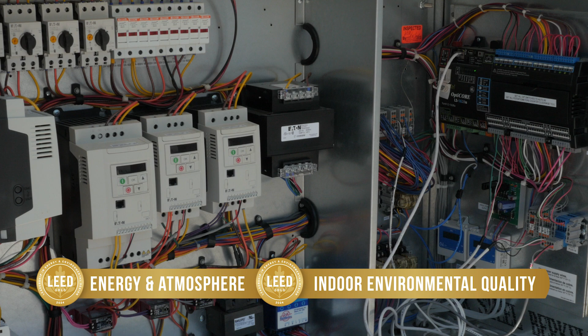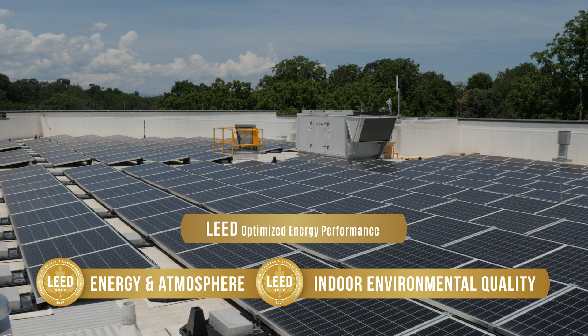Traditional heat pumps have varying levels at which it's too cold to extract heat in freezing temperatures. However, these VRF units can still extract and provide heat at temperatures as low as -10 degrees. This is the first installation of VRF units in the city, and they're the reason the building's occupied conditioned space works without using natural gas. The system also contributes to LEED optimized energy performance in the Energy and Atmosphere category.